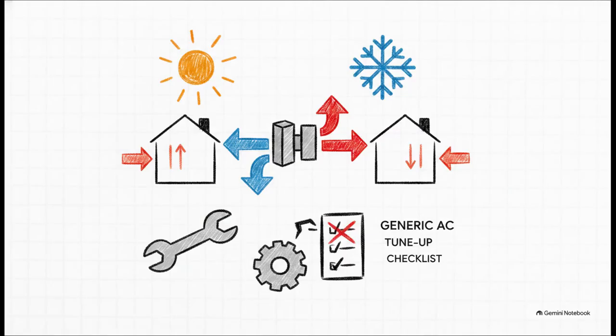The real magic behind a heat pump is something called the reversing valve. It physically reverses the flow of refrigerant. And that's exactly what allows the system to push heat out of your house in the summer and then pull heat into your house in the winter. Because it works so incredibly hard, it's a prime candidate for wear and tear. And guess what? A generic AC tune-up checklist completely ignores it. Why? Because standard ACs simply don't have one.